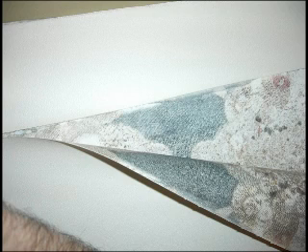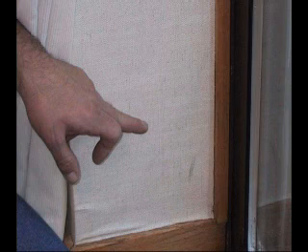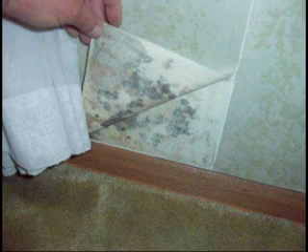food, fungal reservoirs begin to amplify in these areas, coupled with hotel designs where the bathroom vents are all connected up to the rooftop where a fan is sucking that room. So now you have a room that sucks. It's basically being depressurized. It's sucking the air right out of that room. So if you suck air out of the room, new air's got to come into the room. Well, it's going to come through cracks, walls, etc.